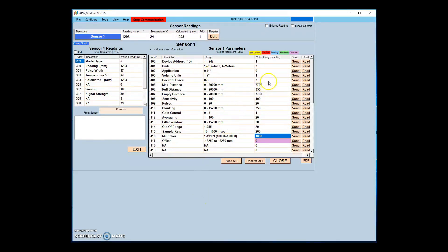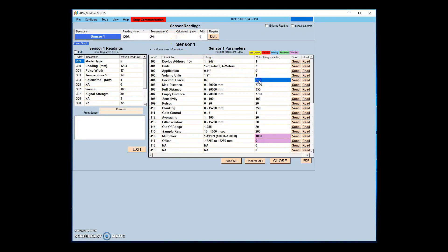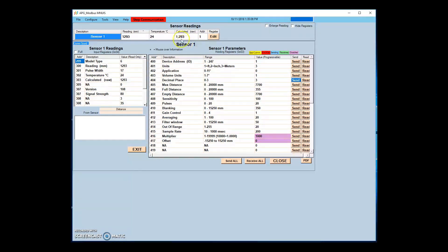The decimal place parameter determines how the reading from the sensor will be rounded. For instance, if the sensor reads 1.293 meters and the decimal place is set to 0, 1 meter will be displayed. If the decimal place is set to 3, the full value of 1.293 will be displayed.